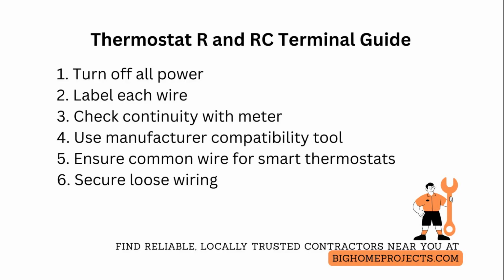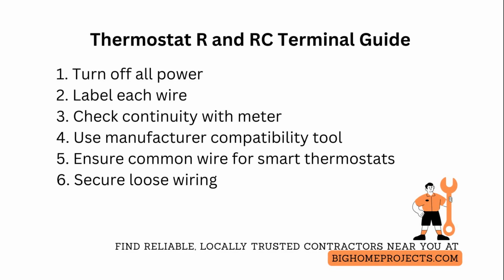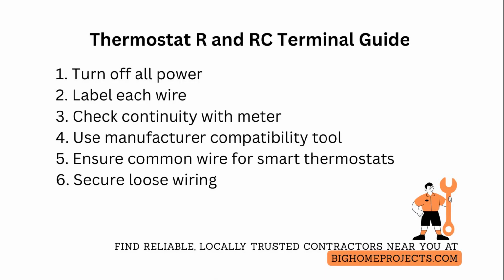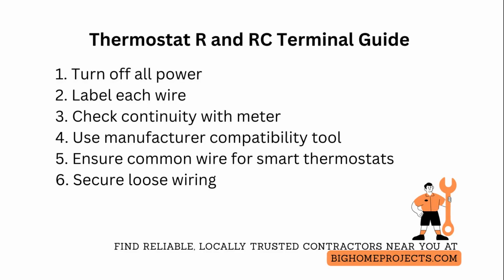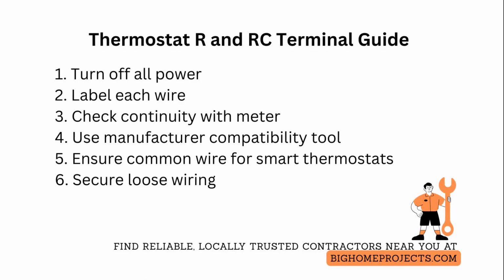Modern smart thermostats often require a common wire, so plan for a C conductor or a power extender kit. If you see only one R and no RC, assume R powers both and do not add or remove jumpers. If replacing an older mechanical stat with a digital or smart unit, confirm the new unit supports two transformer isolation or provides instructions to remove the jumper.